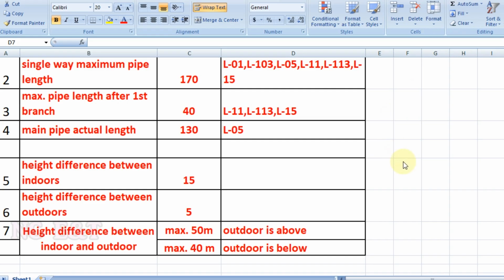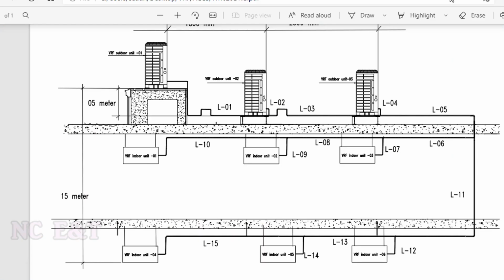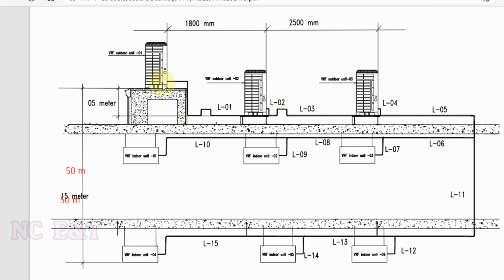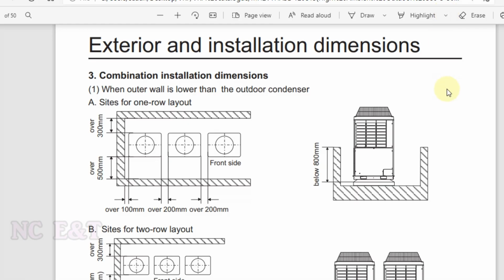Number 7, the height difference between indoor and outdoor units. It is the level difference between the highest outdoor unit and the lowest indoor unit, or vice versa. If the outdoor unit is above, it can be 50 meter maximum. If the outdoor unit is below, it can be a maximum of 40 meter. For example, if we keep the outdoor unit on top, the height difference between the lowest indoor unit and the outdoor unit can be a maximum of 50 meter. If the outdoor unit is below and the indoor unit is above, then we can have a difference of only 40 meter.